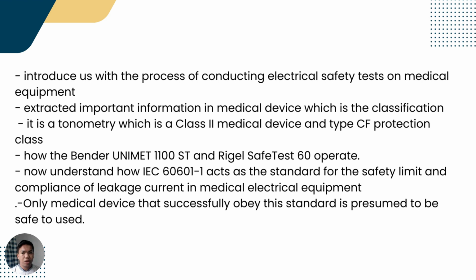Next, we are also aware of how the Bender Unimet 1100ST and the Rigel Safe Test 60 operate, and we also now understand how the IEC 60601-1 acts as the standard for the safety limit and compliance of leakage current in medical electrical equipment. Only a medical device that successfully obeys this standard is presumed to be safe to use. According to our results, the tonometry is considered safe to be used by both patients and operators because all the leakage currents do not exceed the limits.